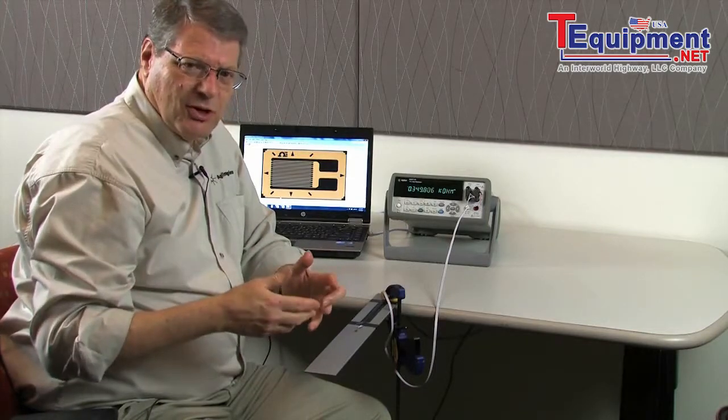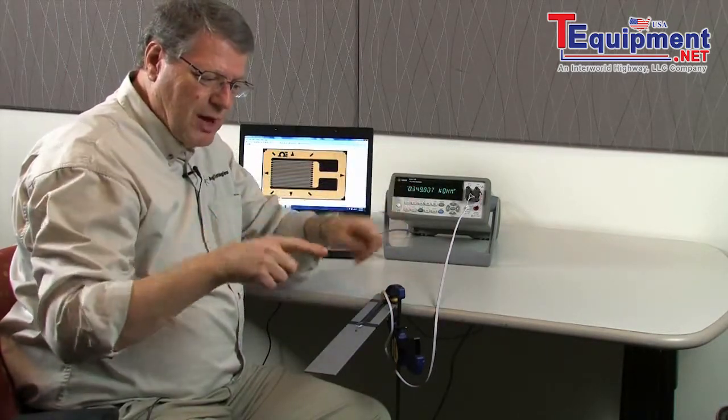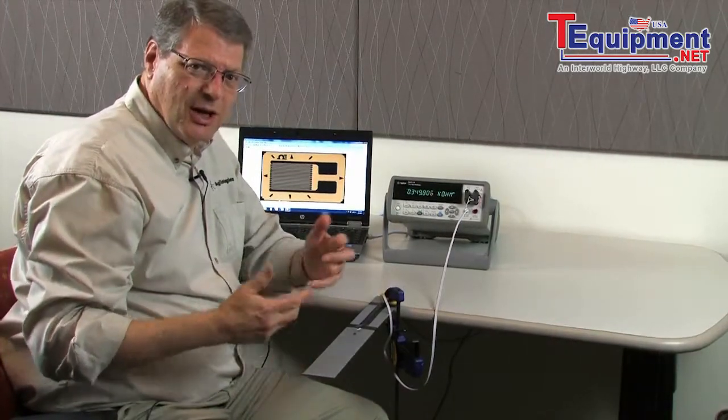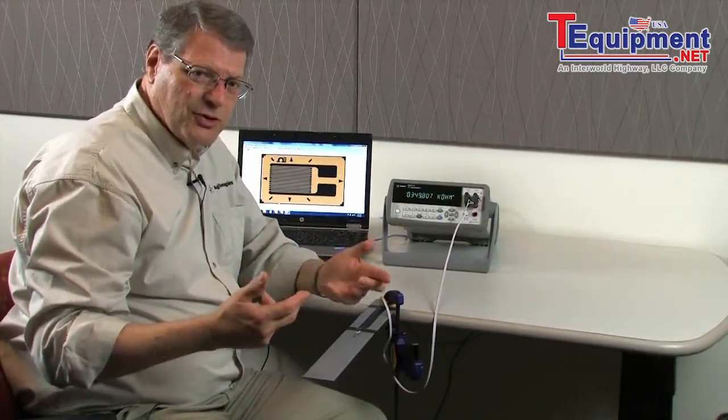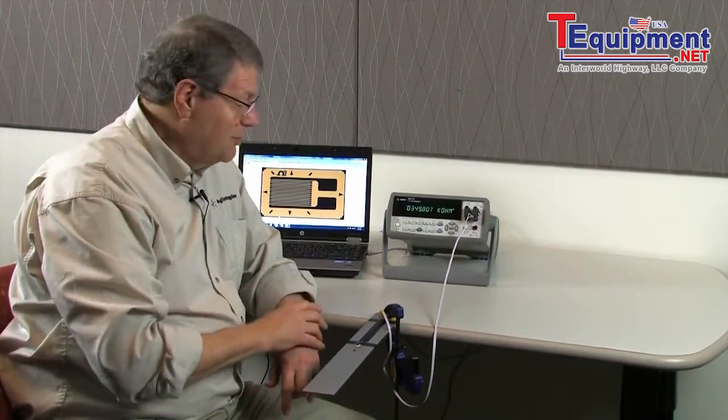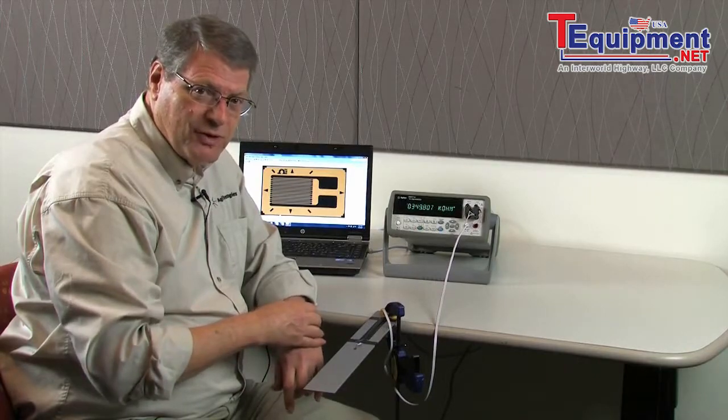The way people usually measure this is they put it into something called a Wheatstone Bridge. They have an excitation voltage, a balanced bridge, and one, two, or four legs have strain gauges in them. And they measure a voltage across it. Well, it's pretty complicated. What I'm going to show you is with the 34411A, we can take a four-wire ohm measurement of that same strain gauge and get a similar result.